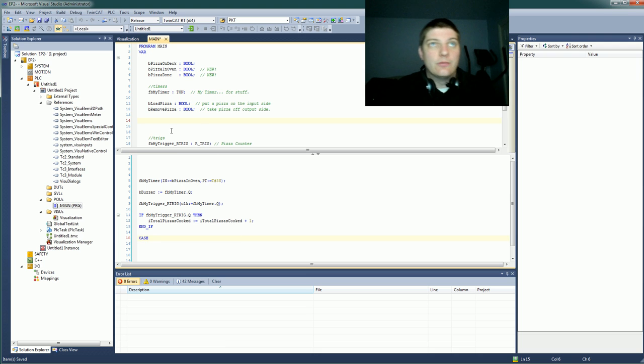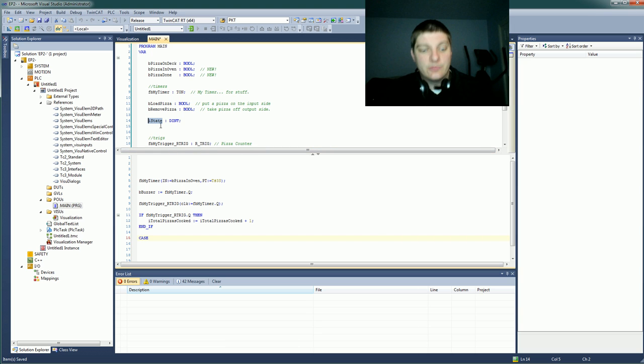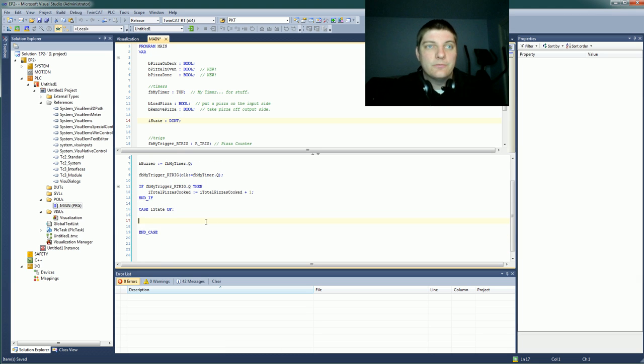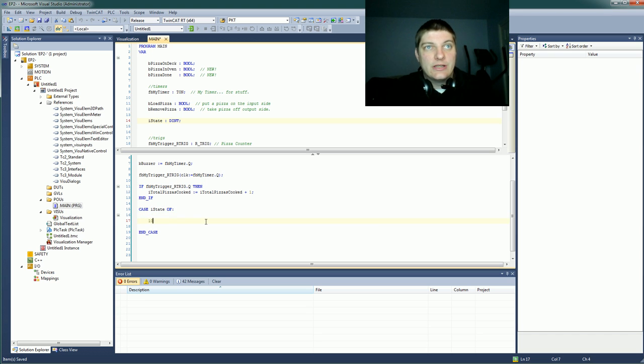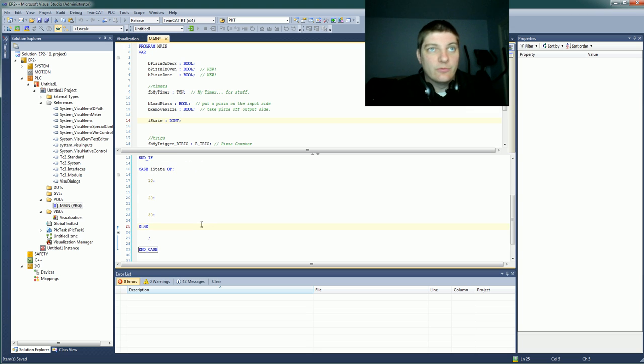On to the case statement, which makes up the state machine. I need a state variable I can track. You can encode these in various ways — name a bunch of constants, all sorts of stuff. The way that works best for me is to simply make an int of states. If you never use negative states, you can use a uint and get a ton more states. So we'll do: case i_state of — and it automatically ends our case statement. What we're saying is this is like an if statement: if i_state equals 10, do some stuff; case i_state 20, do some stuff; 30, do some stuff; else, do some stuff. It's a really complicated if statement that doesn't actually get that complicated very quickly.